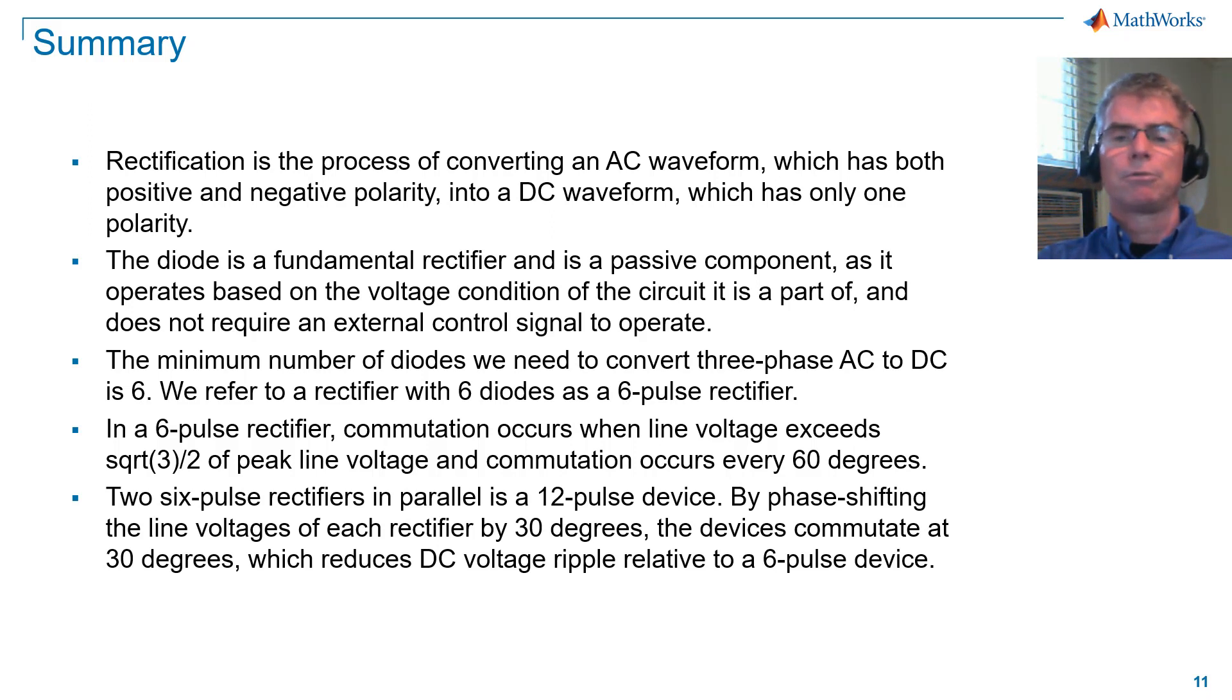Two 6-pulse rectifiers in parallel is a 12-pulse device. By phase shifting the line voltages of each rectifier by 30 degrees, the devices commutate at 30 degrees, which reduces DC voltage ripple relative to a 6-pulse device. Three-phase rectifiers introduce harmonics onto the AC supply.